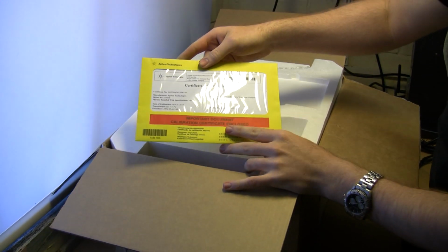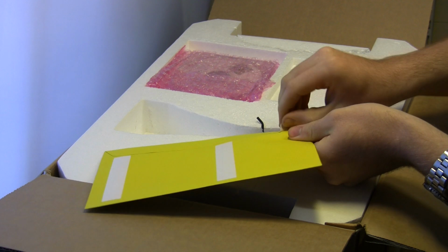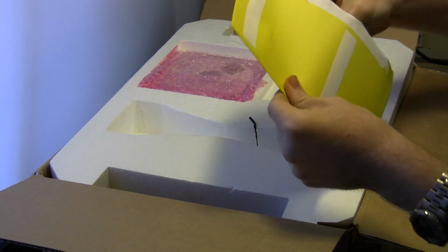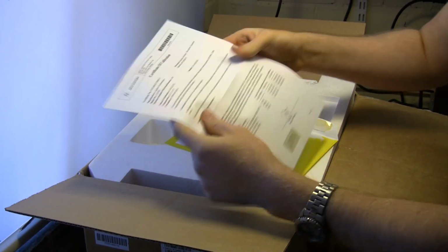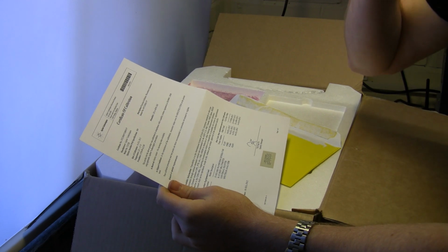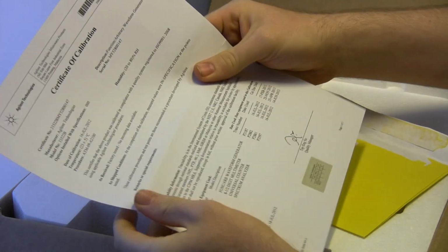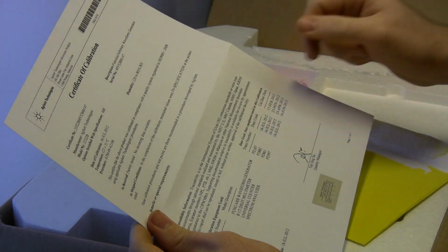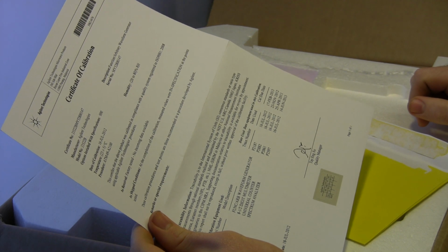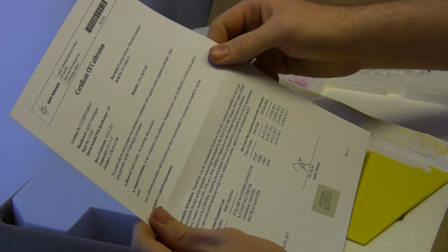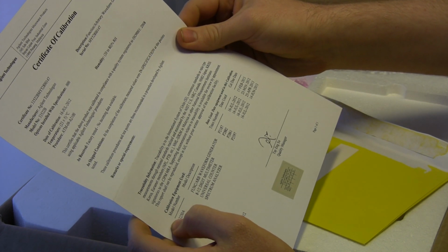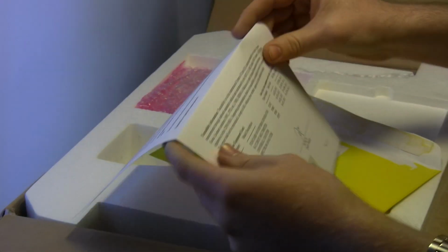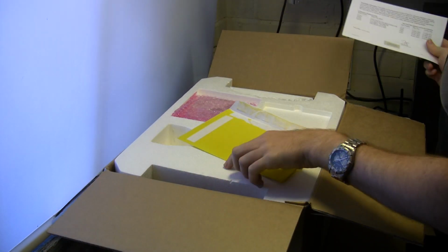and a certificate of calibration. What do they calibrate on this? Right, it doesn't actually give you any numbers at all, but does tell you it's been calibrated using an 8.5 digit multimeter, universal counter and a spectrum analyzer. So presumably they've done the frequency there, and the actual output voltage with the spectrum analyzer. Interesting. Presumably for modulation. Right, put that aside.